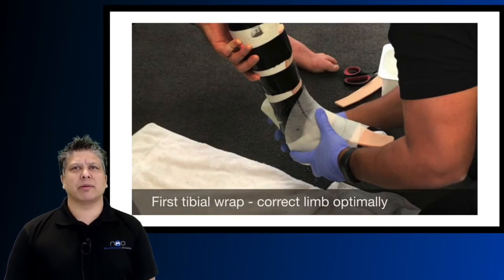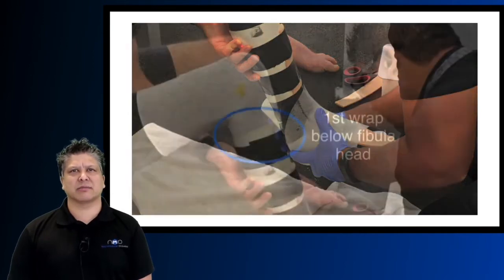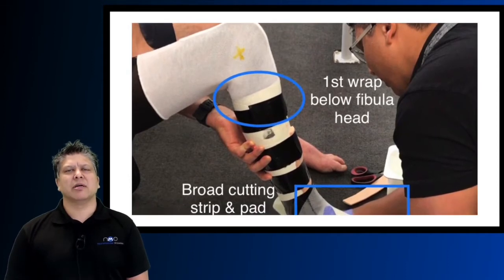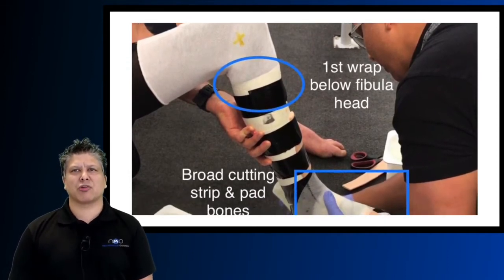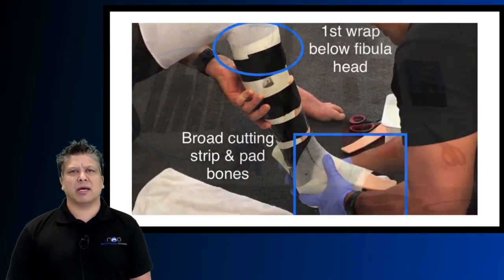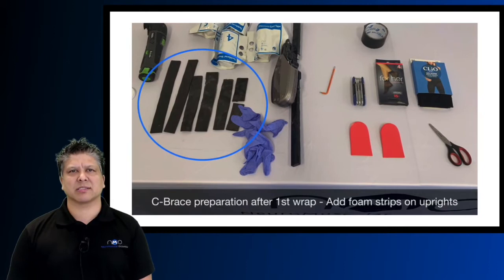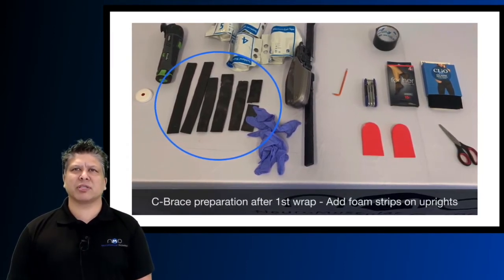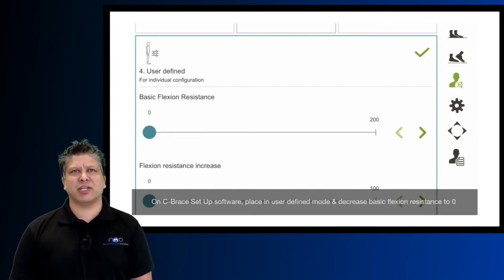For your first tibial wrap, correct the limb optimally as you would in any below-knee AFO cast. The first wrap must start approximately one inch below the fibular head. Place a broad cutting strip across the ankle dorsum and pad any bony prominences susceptible to pressure. Prior to your first wrap, on your C-Brace setup software place it in user-defined and decrease your basic flexion resistance to zero.